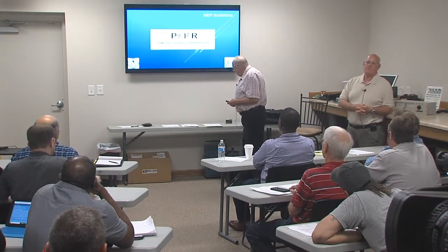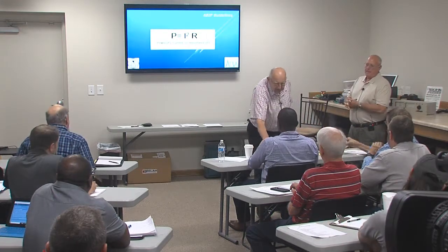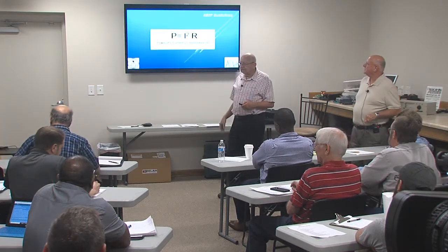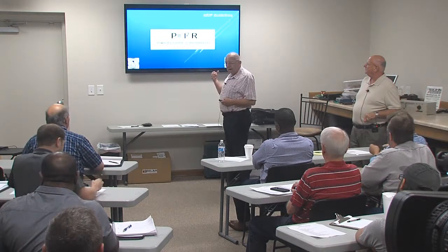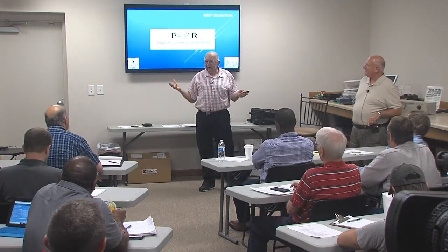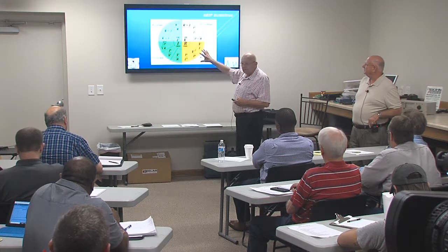This is the actual formula. To be an inspector you do have to use a formula. This is an Ohm's Law chart. You have to know a little bit of math to figure out how to do this. If you go out to the tower to figure out what the power is, Ohm's Law says power equals the current squared times the resistance - P = I²R. You have to look on the license and see what the resistance of the tower is. If you knew the power and the resistance and needed to know the current, you divide the power by the resistance and take the square root.